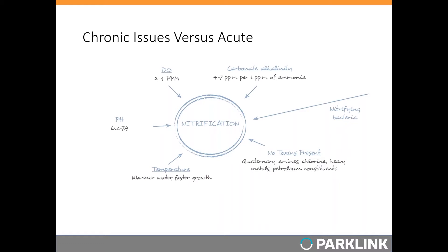Looking at common acute issues where nitrifying bacteria are lost: one major reason is high flow rates. If a rainfall event leads to higher-than-average flows, the plant may get washed out and lose a lot of bacteria. Even if they don't lose half their mixed liquor, nitrifiers only make up a small percentage of the bacteria, so losing even a moderate amount of mixed liquor will greatly magnify the impact on the nitrifying bacteria population.